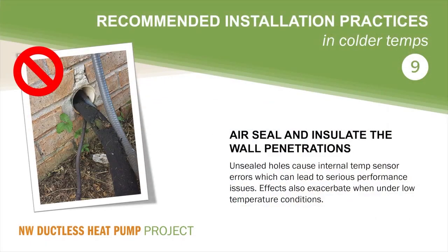For our final recommended installation practice, we have a reminder to air seal and insulate all wall penetrations. Unsealed holes can cause internal temperature sensor errors, which can lead to serious performance issues. The effects of unsealed wall penetrations are exacerbated under low temperature conditions. Unsealed wall penetrations are a common installation oversight and point to an opportunity to create an installation checklist containing reminders for all of these necessary installation items.